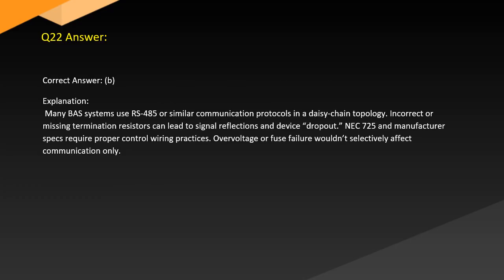Answer. Correct answer: B. Explanation. Many BAS systems use RS-485 or similar communication protocols in a daisy-chain topology. Incorrect or missing termination resistors can lead to signal reflections and device dropout. NEC 725 and manufacturer specs require proper control wiring practices. Overvoltage or fuse failure wouldn't selectively affect communication only.